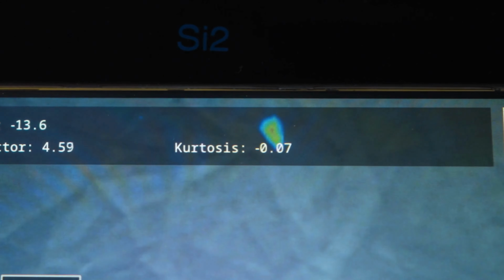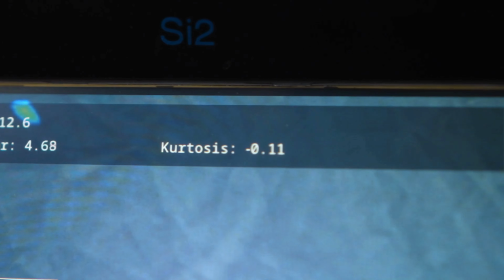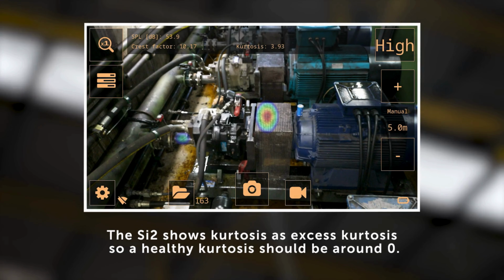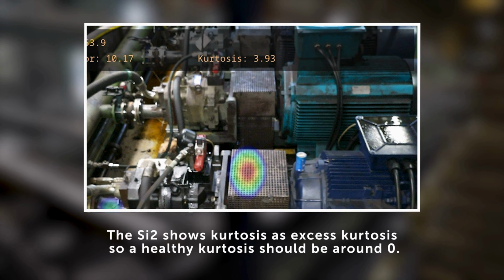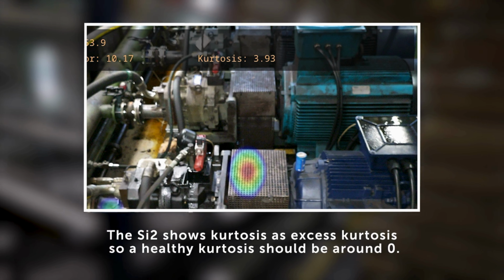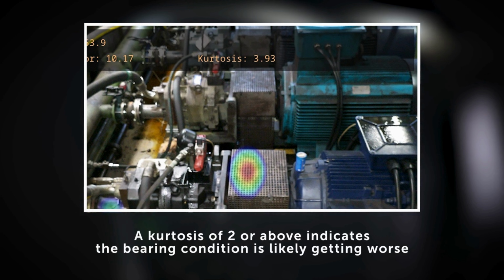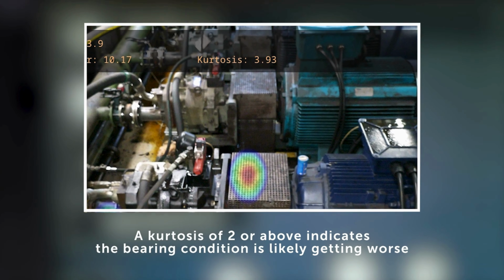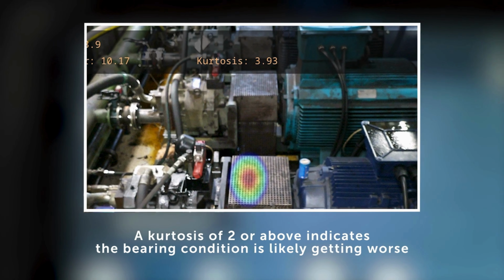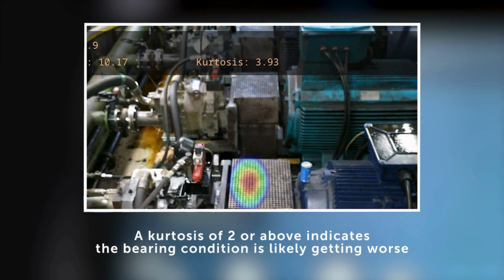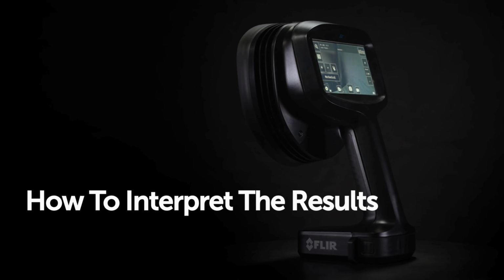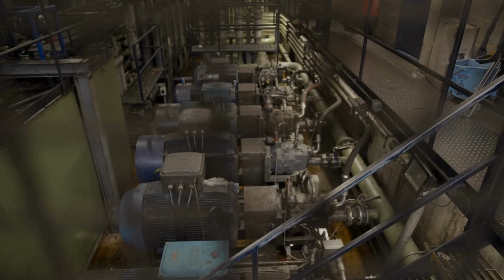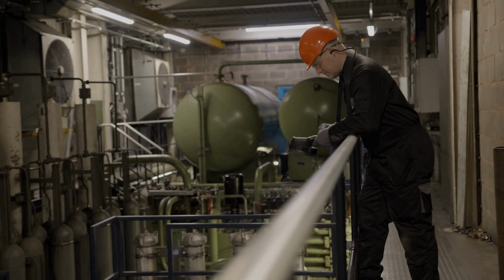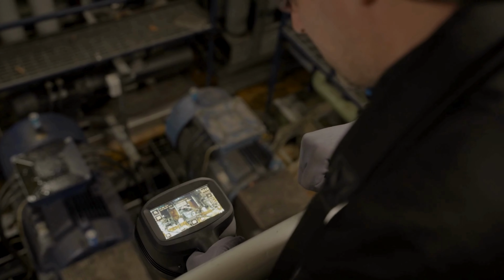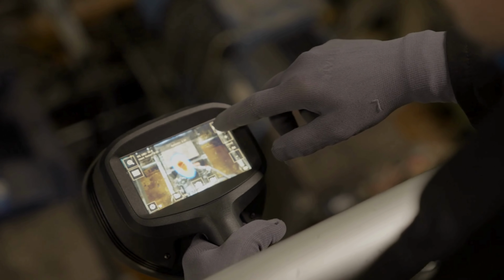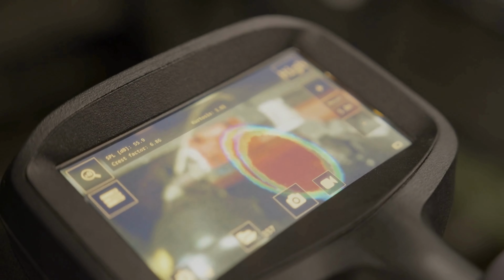Kurtosis is a measure of the distribution of the samples in the sound signal. The Si2 shows kurtosis as excess kurtosis, meaning that a healthy bearing will show a kurtosis around 0. A kurtosis of approximately 2 or above is likely to indicate that the bearing condition is getting worse. It is recommended to always compare the crest factor, kurtosis, and SPL of a bearing to healthy bearings of the same type, measured from a similar distance.